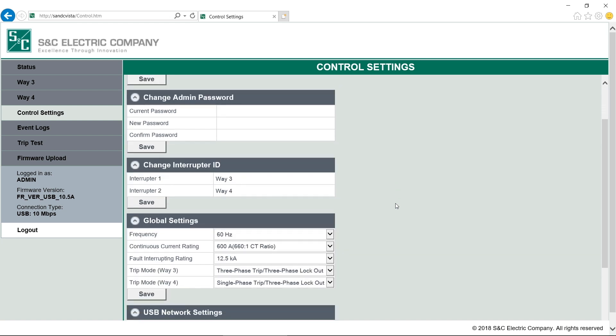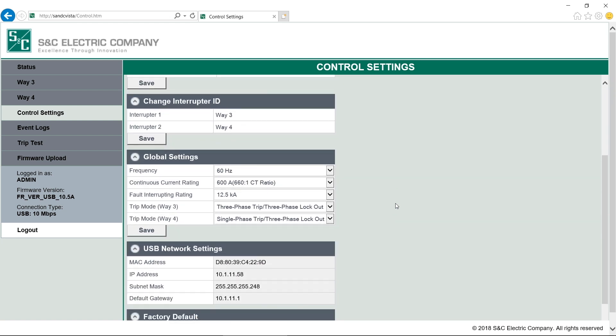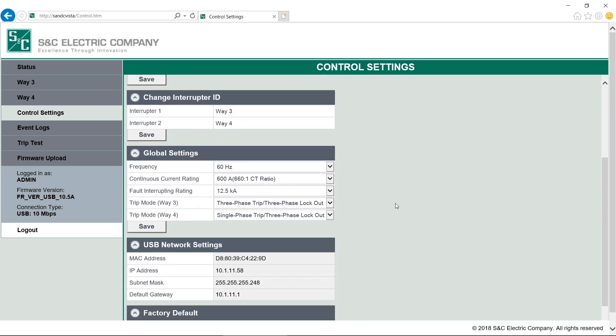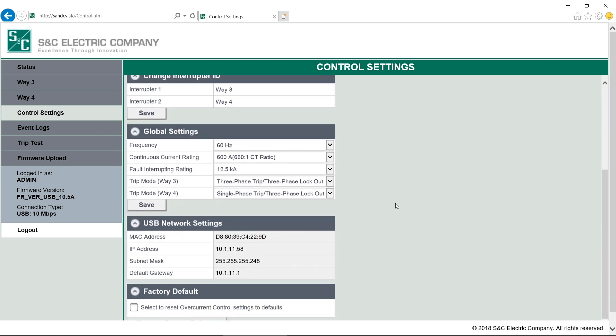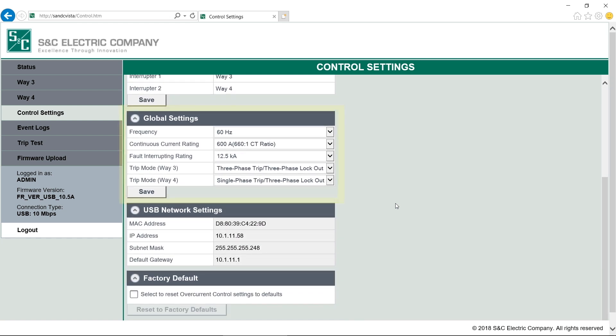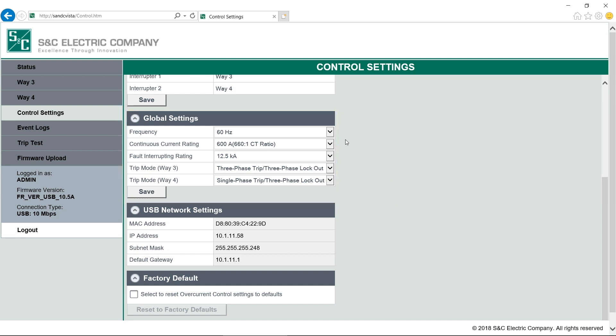The Global Settings menu is next. Here you'll find the switchgear frequency, the continuous current ratings, the fault interrupting ratings, and the trip mode section for both WAYs. S&C will have programmed these settings at the factory. It's important to check that all of these settings match the nameplate on the switchgear. The trip mode setting can be changed here. See the written instructions for the different trip modes. If the switchgear is being used on a 50Hz system, you can change that here.